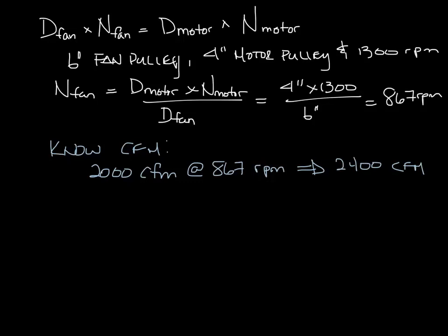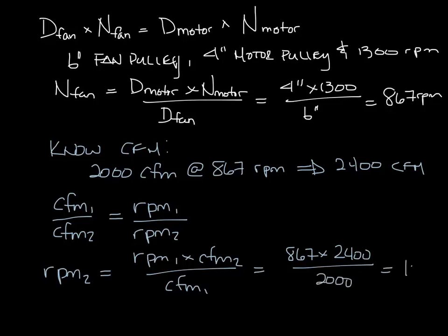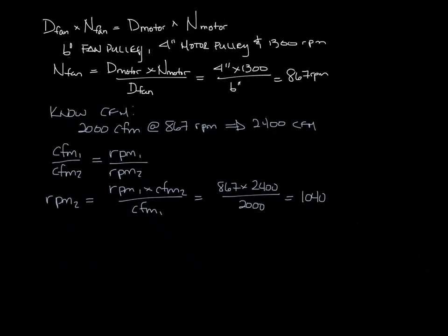So let's use the first fan law, which is CFM1 divided by CFM2 equals RPM1 divided by RPM2. We can solve that for RPM2, which is now equal to RPM1 times CFM2 divided by CFM1. So let's put in our numbers, 867 times 2400 CFM we want divided by the 2000 CFM we have is 1040. So that's 1040 RPM is what we need out of this fan.